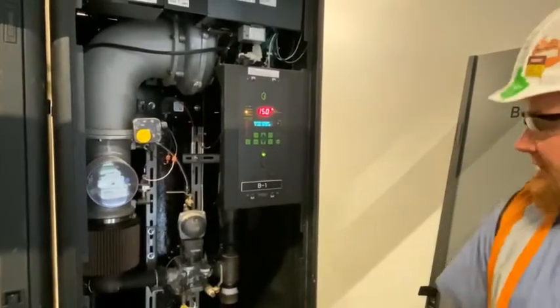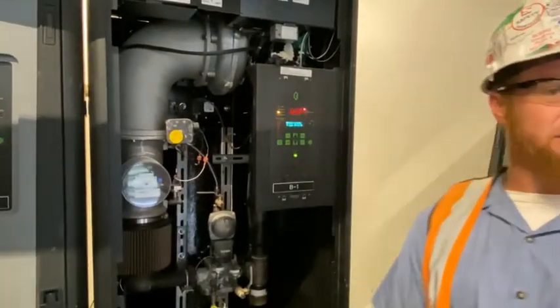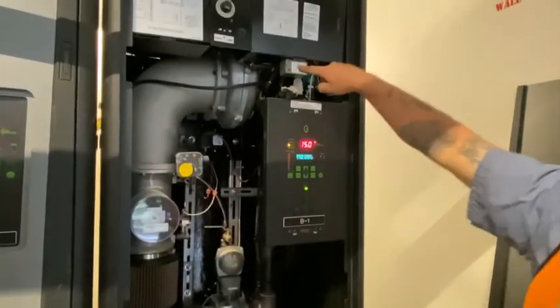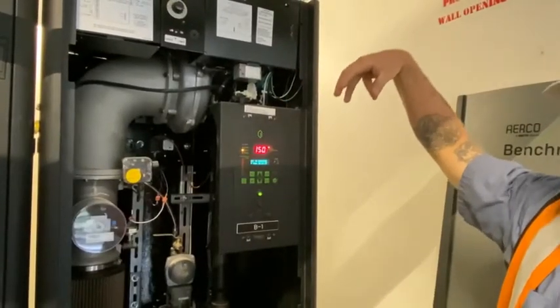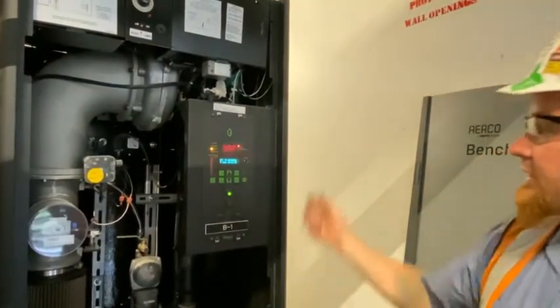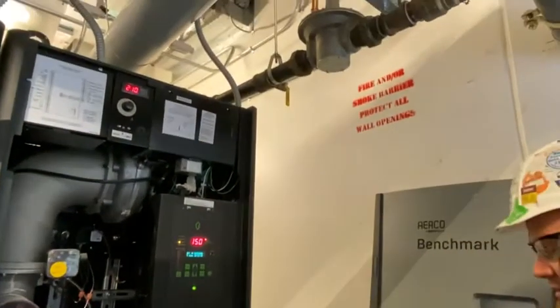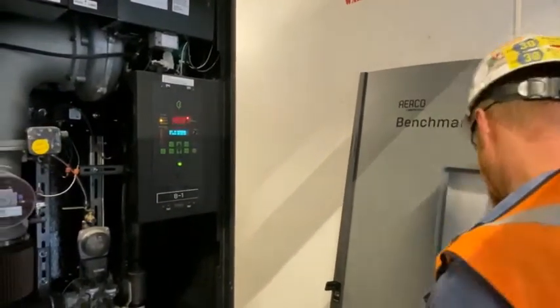It's kind of like a throttle body on a car. There's a K&N air filter on it — it's factory. Cleaning that is just like any K&N air filter — you've got the oil and the washing kit. Then you have an ECM motor, flowing down with a low-NOx burner sock — kind of glows like a kerosene lantern. We're blowing down through the heat exchanger and then back up and out. All the condensate goes down the bottom.